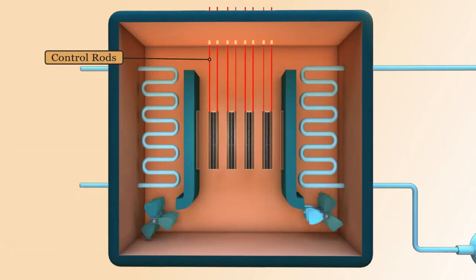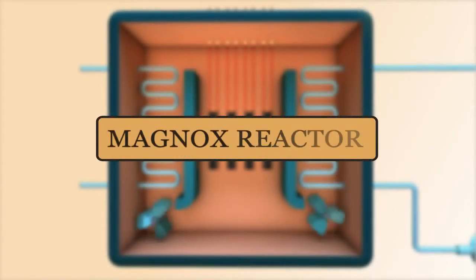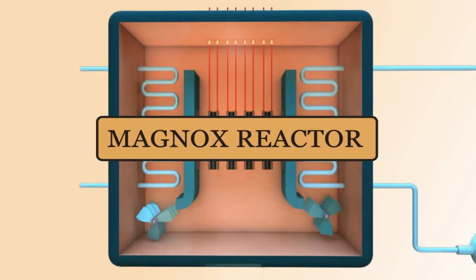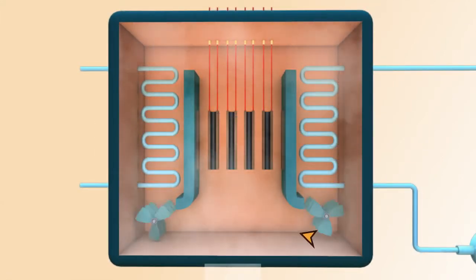Control rods are inserted into the graphite block. Natural uranium is used as fuel and is clad in a magnesium alloy called magnox. Hence, this reactor is also called a magnox reactor. The coolant gas CO2 is supplied by a gas circulator and enters the core from the bottom.